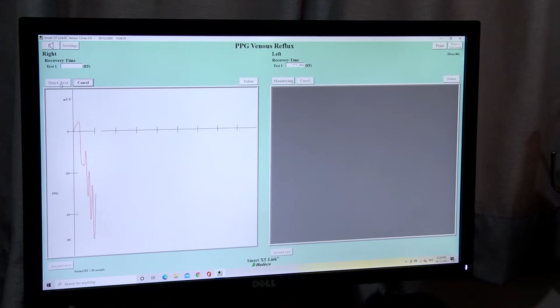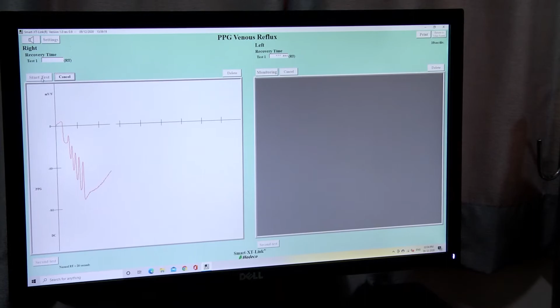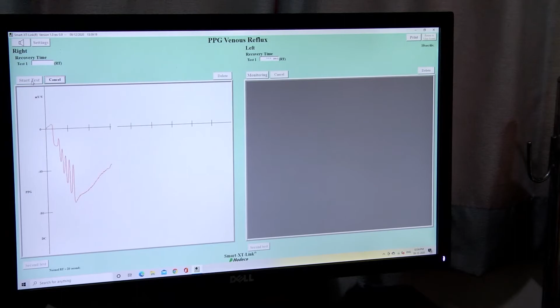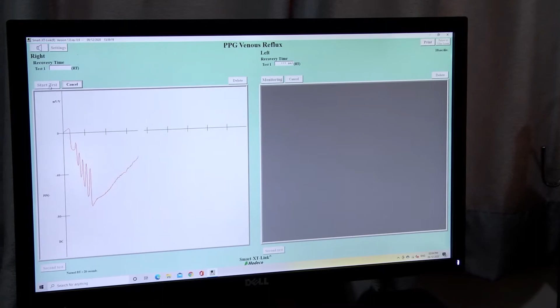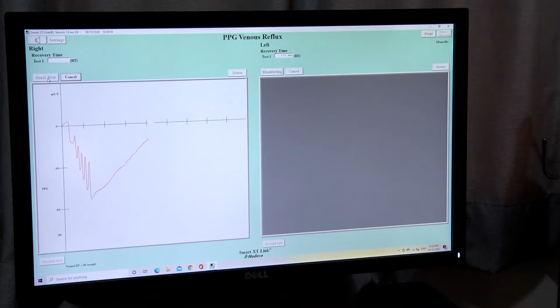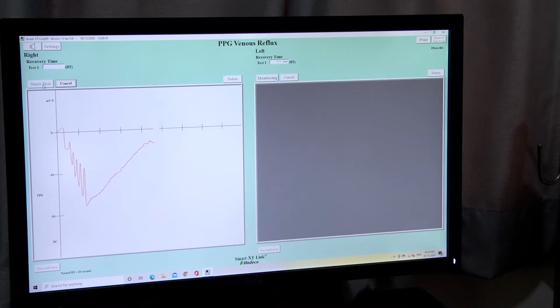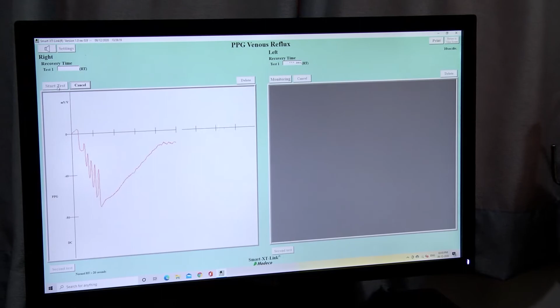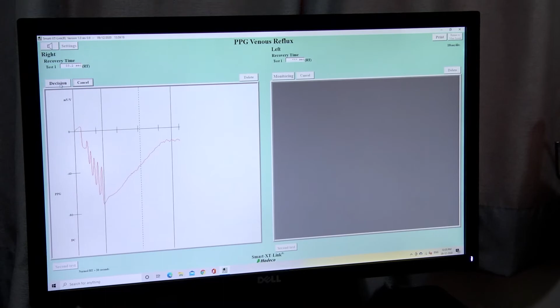For every flexion there should be a change in the venous flow pattern, and once the patient is rested, it slowly comes back to the original baseline position. The time taken for reaching the original position is referred to as the refilling time. If it is more than 20 seconds, there is no valvular incompetency. The valve is competent to push the blood upwards. Once it reaches the baseline, the recording is completed automatically. This is a study which helps prevent deep vein thrombosis.